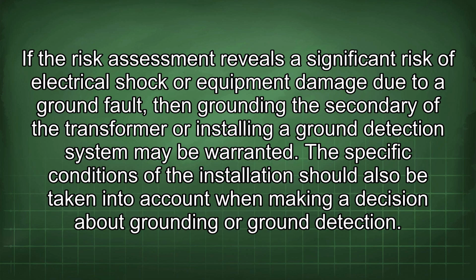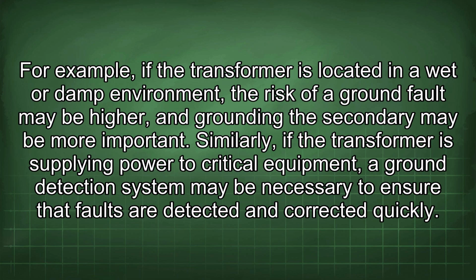The specific conditions of the installation should also be taken into account when making a decision about grounding or ground detection. For example, if the transformer is located in a wet or damp environment, the risk of a ground fault may be higher, and grounding the secondary may be more important. Similarly, if the transformer is supplying power to critical equipment, a ground detection system may be necessary to ensure that faults are detected and corrected quickly.